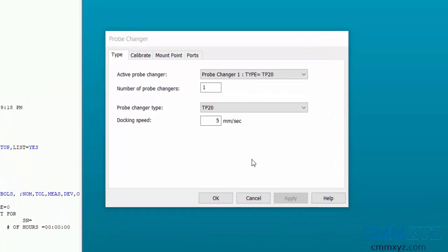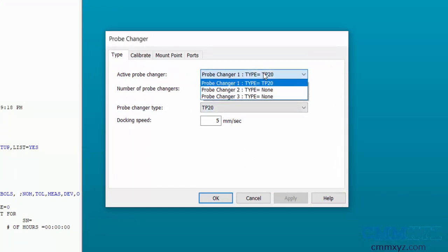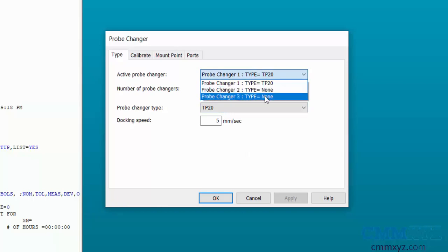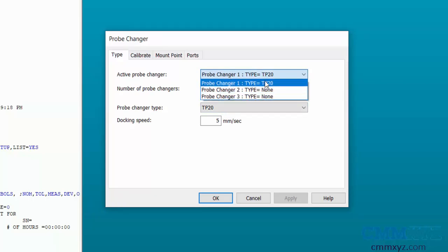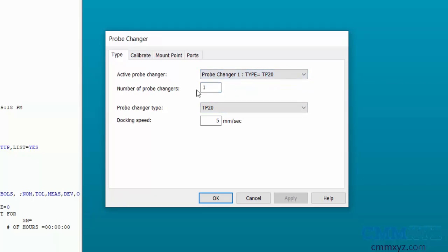If we have more than one probe changer, then enter the number of probe changers and define individual probe changers. Keep the docking speed at a default value of five millimeters.